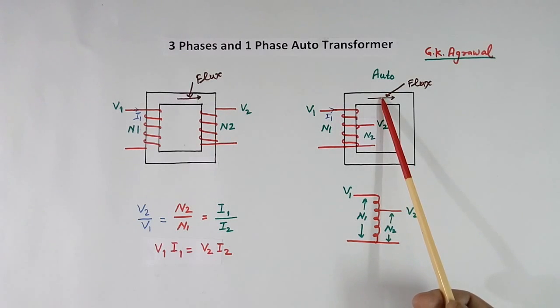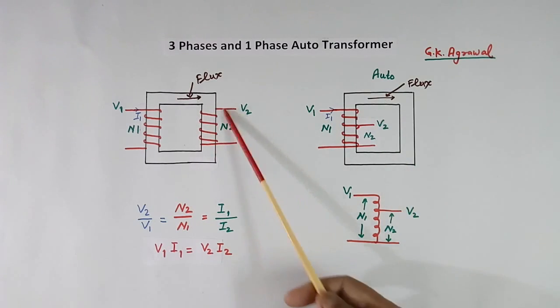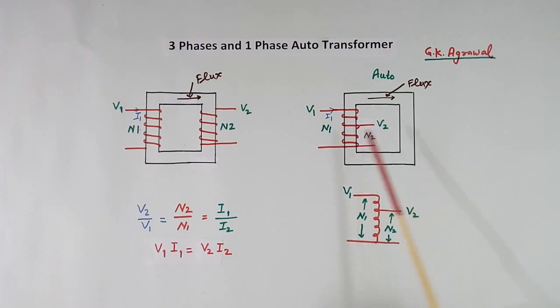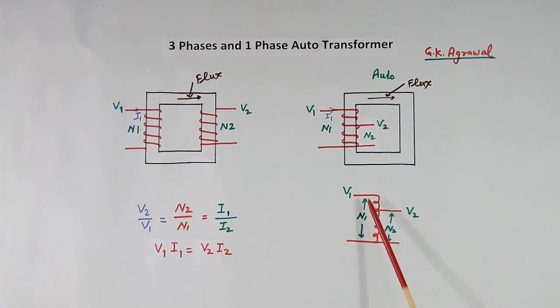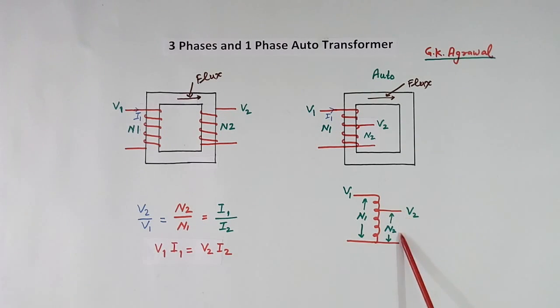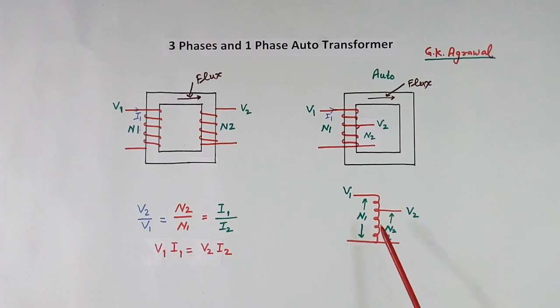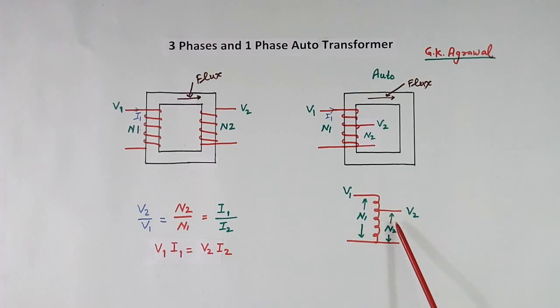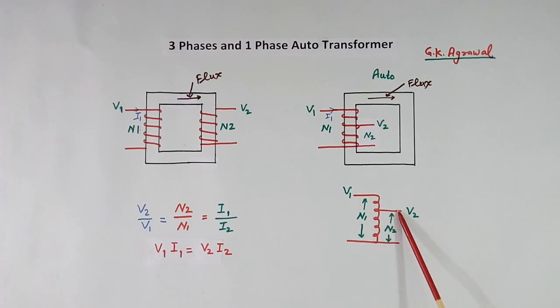In case of an auto transformer, the secondary winding will not be there. Only one winding will be there. From this winding, we take a tap and use it as output. Here we connect a load, and here we connect the AC input. The difference is, because there is no separate winding, there is no isolation. The input and output electrical circuits are connected together.